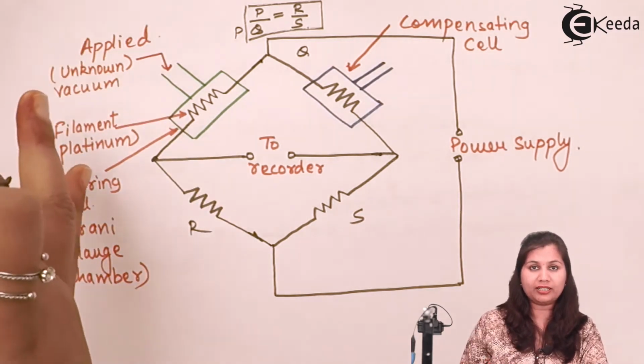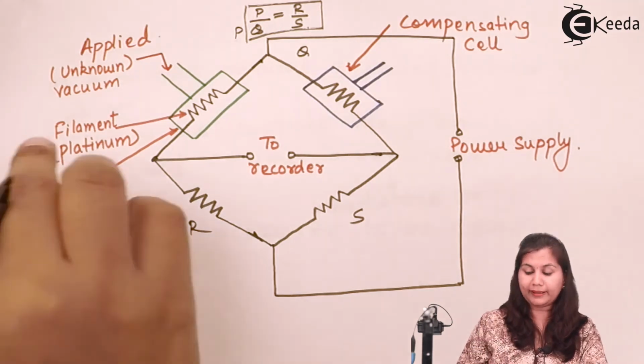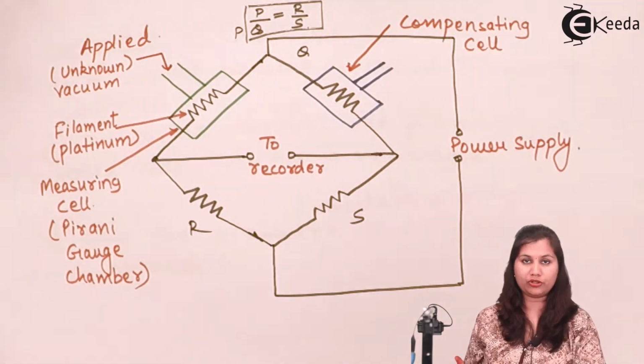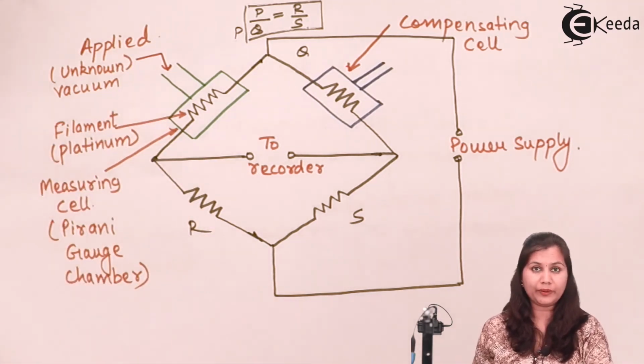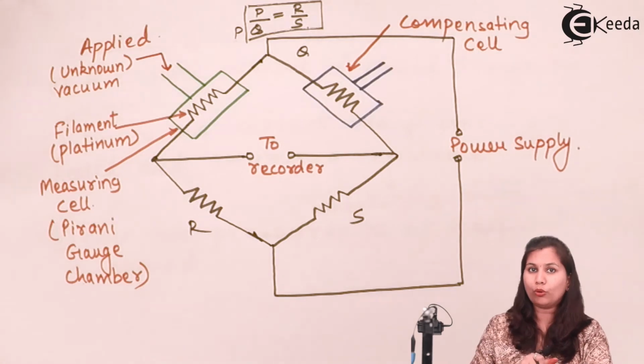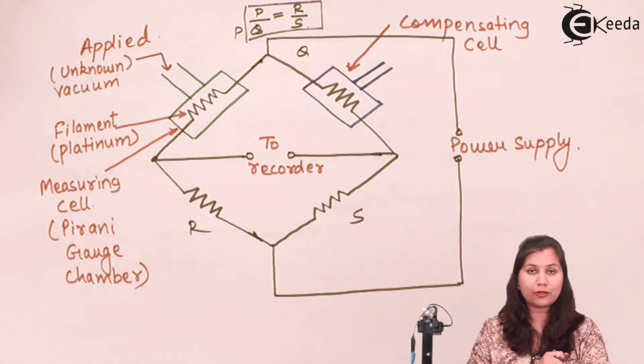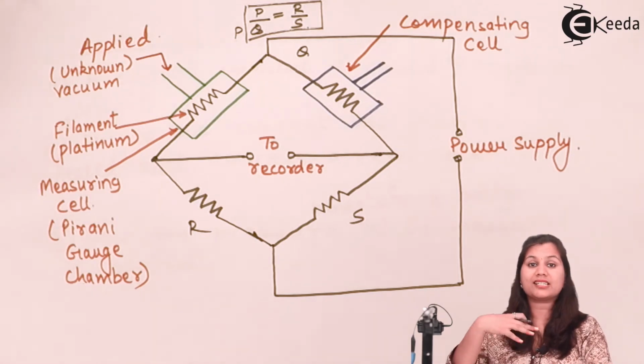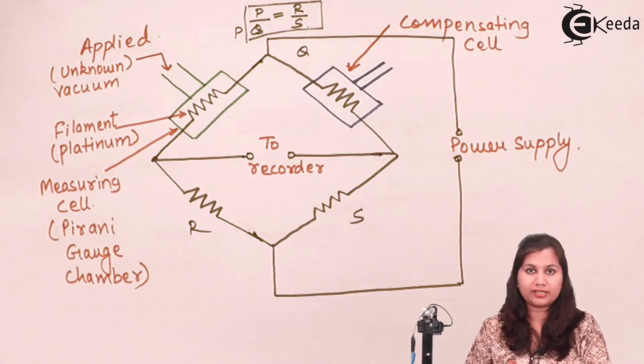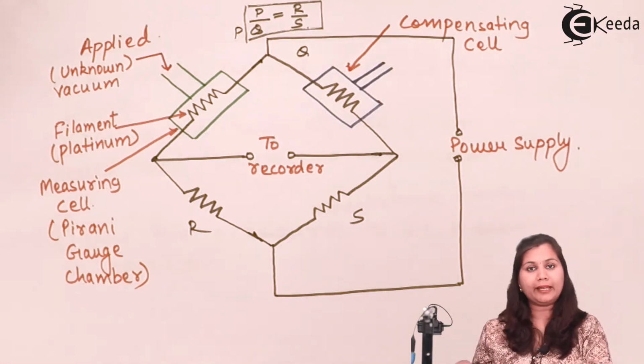So what we are doing, we want to change the conductivity of this filament. For the change in conductivity, we are changing the density of the surrounding media by applying the pressure on it. So when we apply the pressure which we want to measure, the density of the surrounding medium is going to change, and due to the change in the density, the conductivity is going to change. The conductivity is changing means the flow of current is changing. It means that the resistance is also changing, because when conductivity is decreasing, the flow of current is decreasing, and resistance is increasing. So there will be a change in resistance, and that change in resistance will be again measured by the Wheatstone bridge. So now we have applied the pressure on the filament.